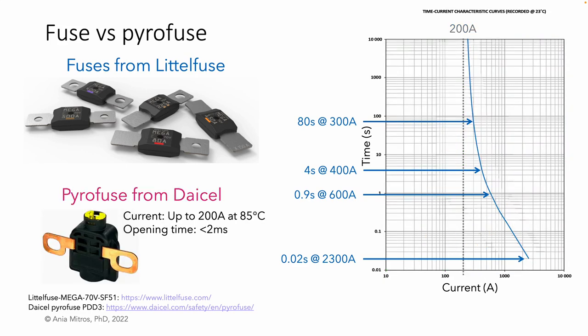Let's compare that to a pyrofuse designed for a similar maximum operating current. A pyrofuse is a more complex, more expensive device with a single spec for operating time. Upon receiving an electronic control signal, the pyrofuse activates an explosive device to rapidly and permanently open a gap between its two power terminals. That opening time is about an order of magnitude faster than the fastest opening times for a traditional fuse.